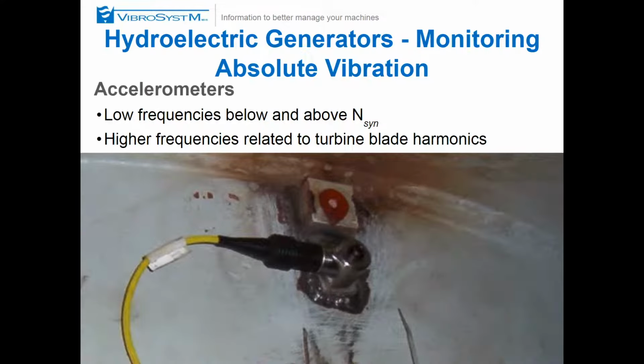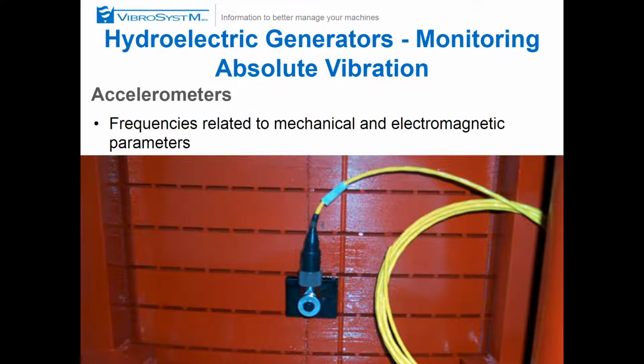Now for accelerometers, to measure the housing, the core, piezoelectric is fine. You don't need to have fiber optic because there's no significant amount of flux there. So the use of piezoelectric is fine. We have a picture here of a sensor looking at the housing. And here we have a picture of an accelerometer looking at the core.